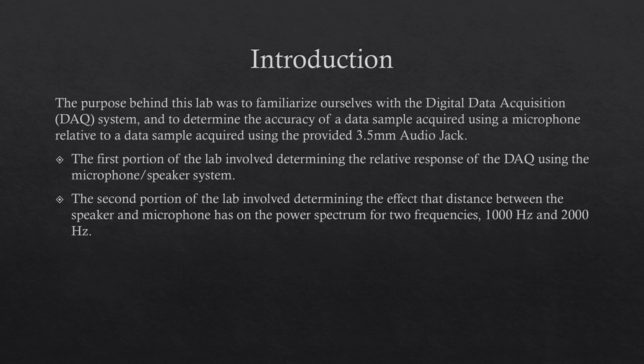When an audio signal is inputted, the LabJack software creates two graphs, a time history graph that depicts the signal's waveform, and the waveform's power spectrum graph, which shows the distribution of energy for different frequencies. The DAQ can only capture data at discrete intervals determined by the sampling rate, the number of samples taken in a second, and the record length, the number of samples in a record.